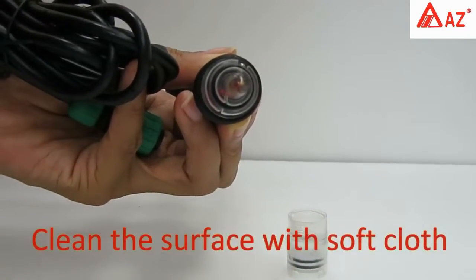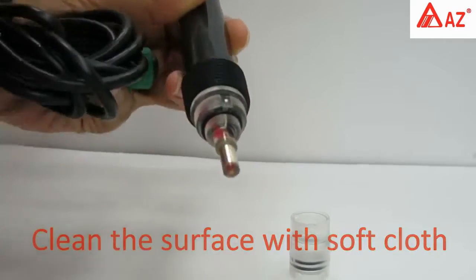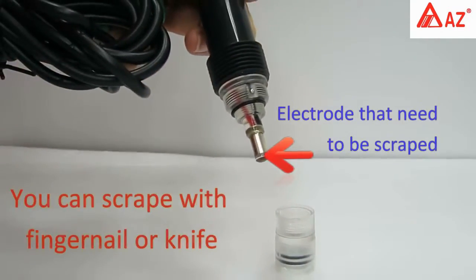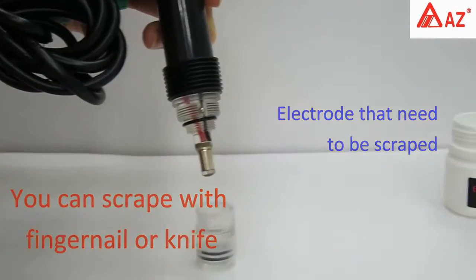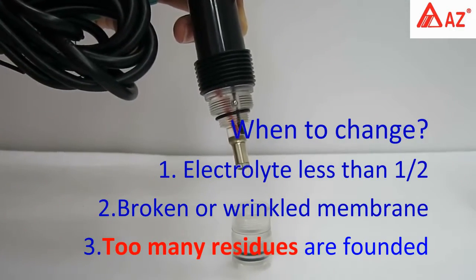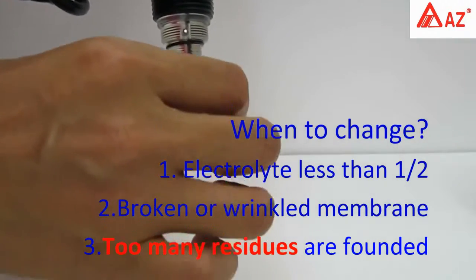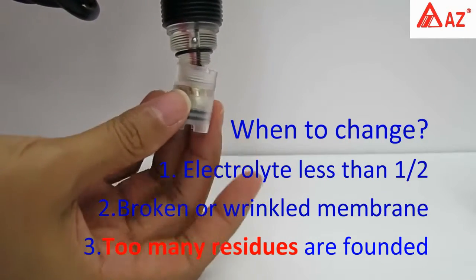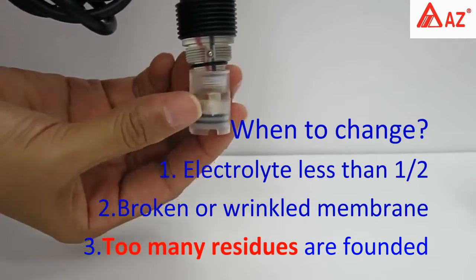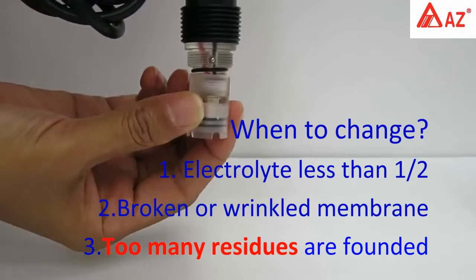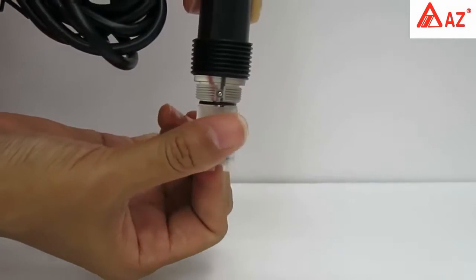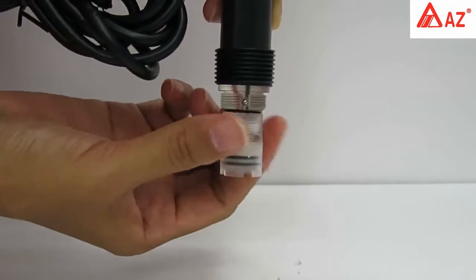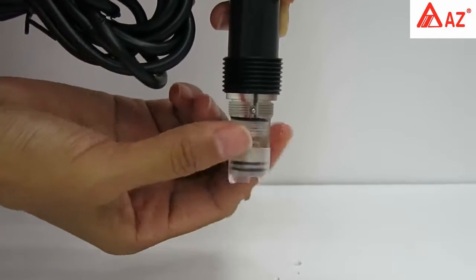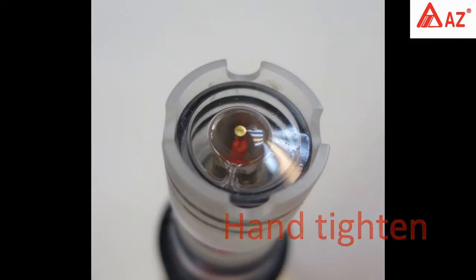Use a soft or long fiber cloth to clean the surface. If the residues cannot be removed by cloth, you can use a fingernail or knife to scrape. When the dissolved oxygen electrolyte is less than half, the membrane is broken or wrinkled, or too many residues are found on the electrode working area, you can change to a new membrane set. Install the new membrane set with full electrolyte, then hand tighten. Rinse with clean water, then wipe it.